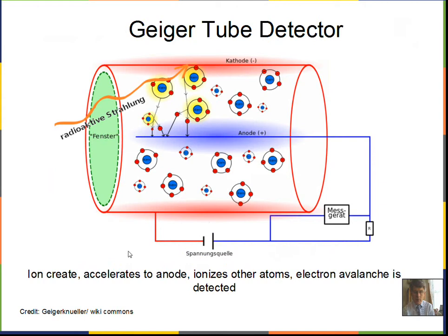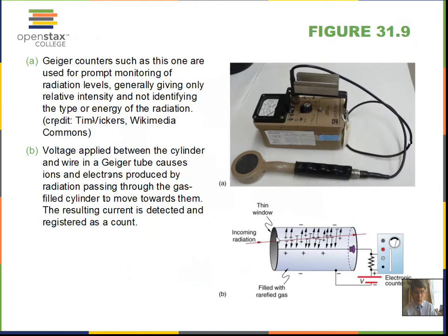Here's a picture of a Geiger counter — a portable device where the meter tells the level of radioactivity. There's a thin window on the tube; this needs to be very thin so alpha particles can get through, and also to allow beta particles to pass through easily, while gammas move on through. One important fact: the Geiger counter does not detect all the radiations that pass through it, especially gammas. There's a certain probability of each radiation type ionizing an atom. For an alpha it's very high; for an electron it's still pretty good. For a photon, maybe only about 10 percent will be detected.